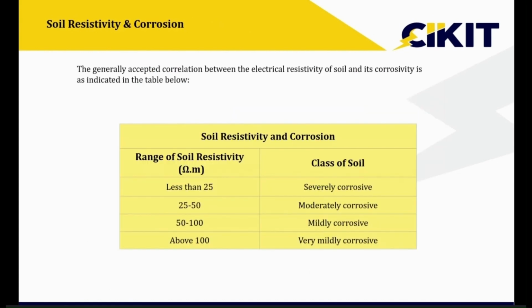The second factor is corrosion. Since we use the earth electrode directly in the soil, corrosion plays an important role. As I mentioned earlier, aluminum is not used for earthing at all. Even though it is a very good conductor, it corrodes much faster when used in the soil. So when working with earthing, apart from conductivity, the corrosion resistance property also plays an important role. Corrosion is associated with the type of soil. If the soil resistivity is much lesser, the soil contains more minerals and salt, and if the minerals and salts are more, the corrosion rate will also be more.